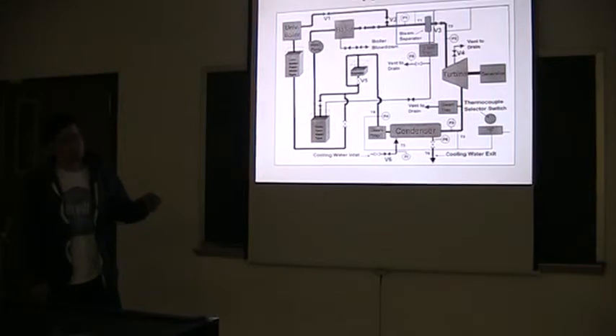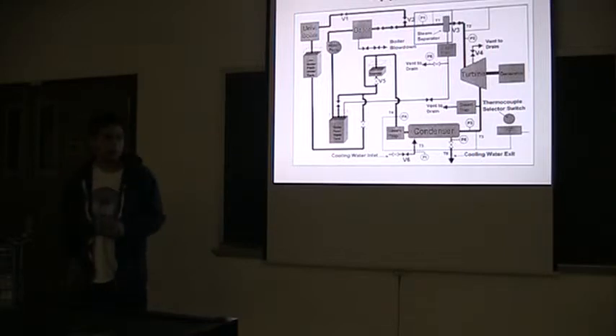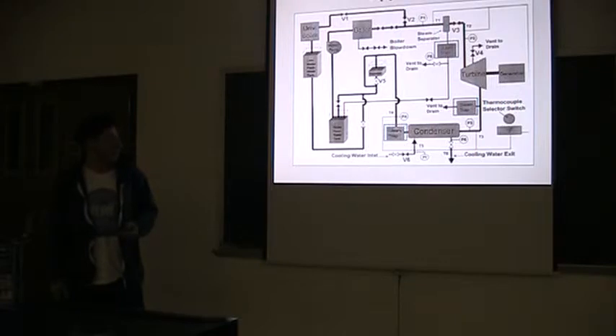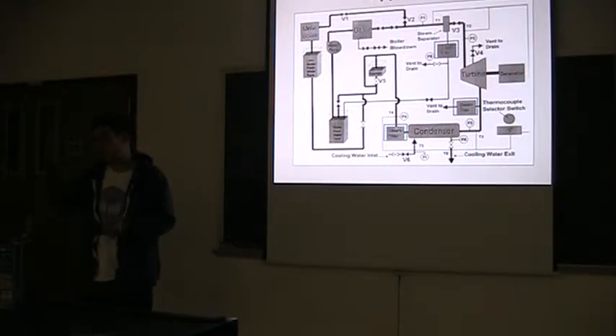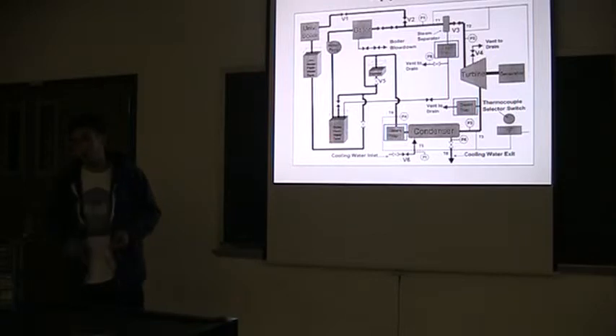We have a steam separator, which is placed before the turbine. This improves the quality of the steam before it enters the turbine. This helps to stop water hammering and also increases the turbine's efficiency. We have steam traps placed throughout the system. Steam traps collect water condensing in them. There's also a boiler feedwater tank.